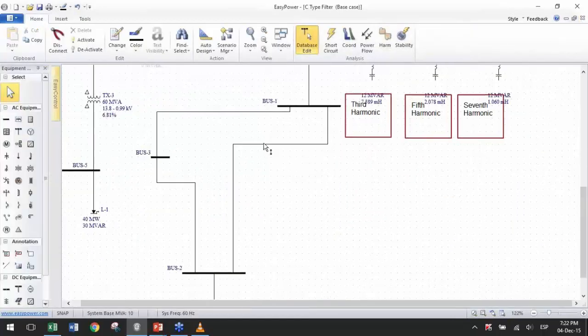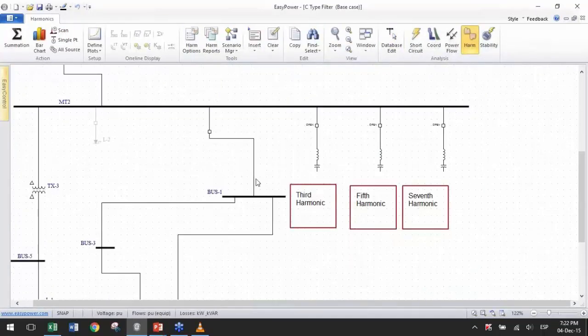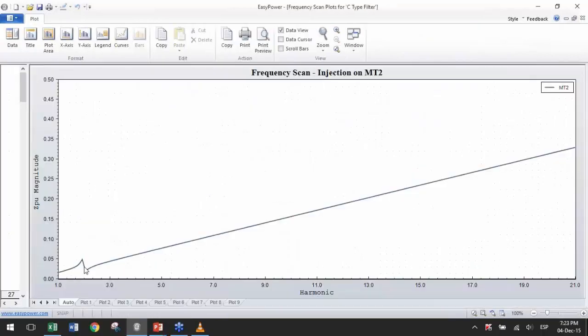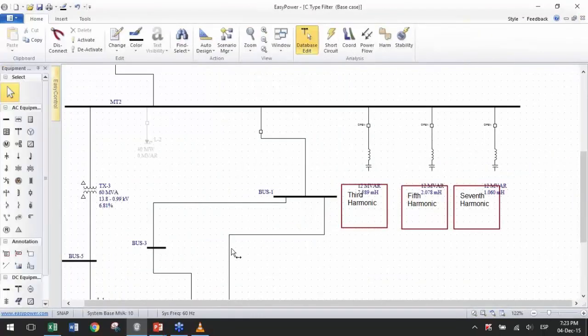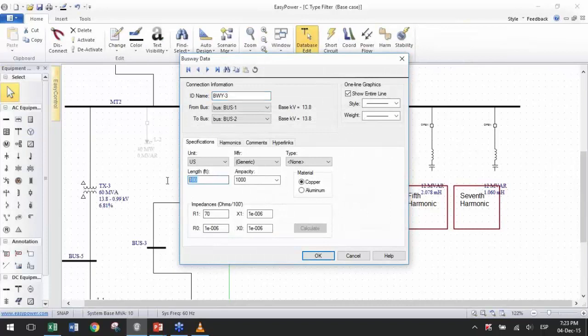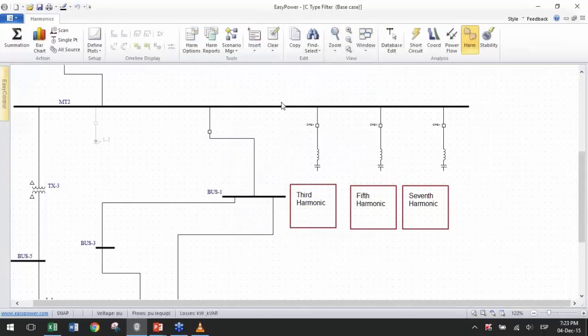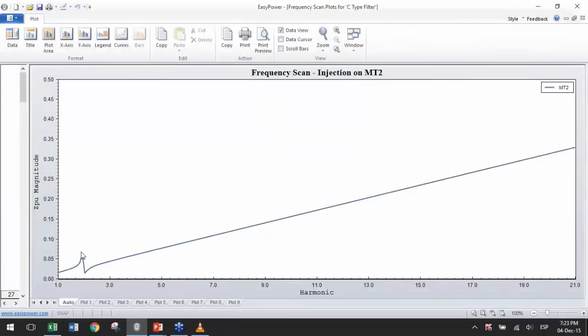Let's see what happens when we change the resistance. So we change the tuning factor, the quality factor. Let's say this is much higher, 70. Now the resonance goes a little higher, and it still works fine. What happens when I add a lot more resistance? The resonance goes higher, much higher, but in all, the filter works very well to attenuate the harmonics because the system is mainly inductive and the resonance is attenuated.